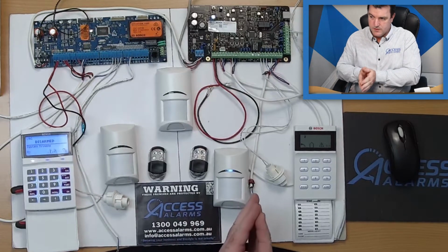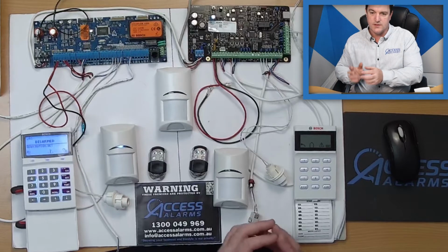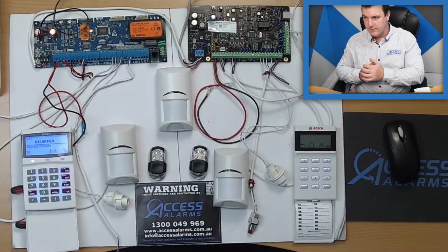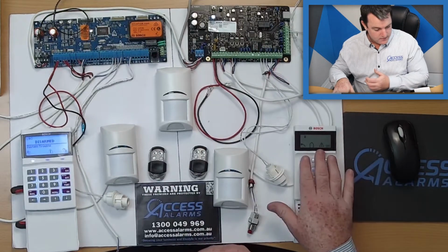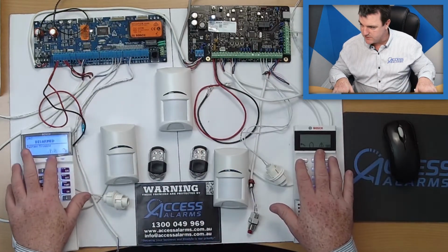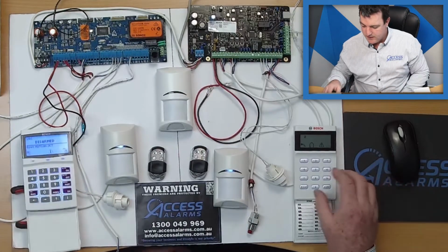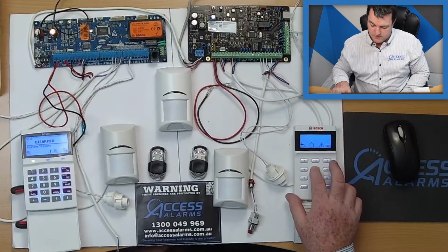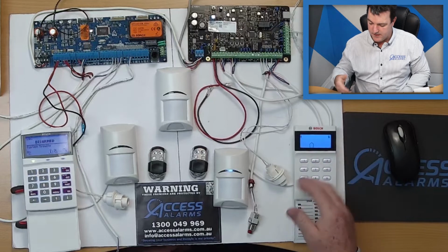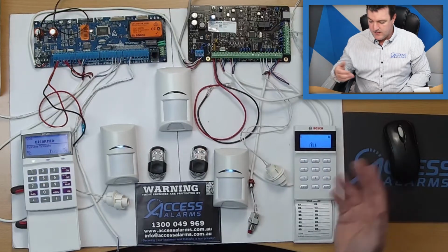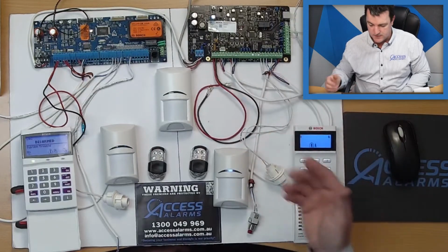If you have a trouble condition or a problem with the 3000 for whatever reason, the 3000 can be very difficult to navigate for you as the end user. If you notice here, when there's a system fault, they both have a triangle with a caution mark with an exclamation in the middle. On the 3000, push and hold 5 and it comes up with a sequence of numbers. It tells me the 1, I push the 1 and now it tells me that there's a 1 and an 8. Which I know is basically the panel tamper and a low battery.